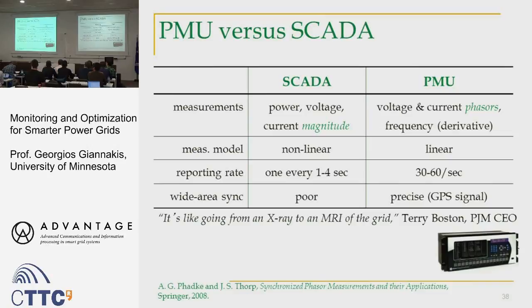PMUs, on the other hand, promise to measure not only amplitude but also phase — and therefore the entire phasors. By taking the derivative of the phase you can find the frequency. Although conventional meters give rise to quadratic equations, PMUs, because they go with Ohm's law rather than power, give rise to linear equations. They report 30 to 60 measurements per second, and synchronization is very precise because they use GPS synchronization.